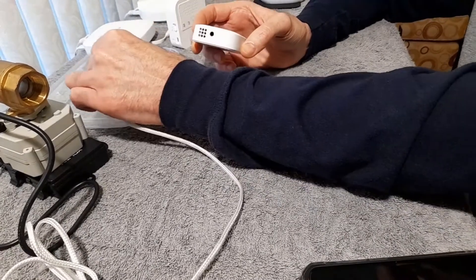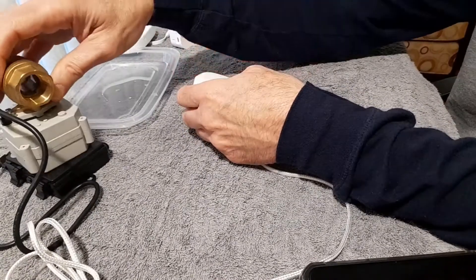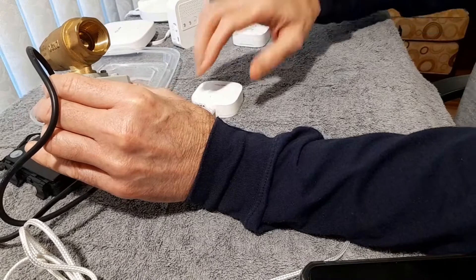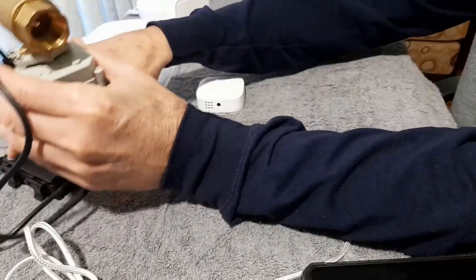This cable has been previously put in water here. So when this thing makes contact, it sets off the alarm and it actually closes the valve. So we can open the valve back up, and we'll just go through that one more time just to show you.